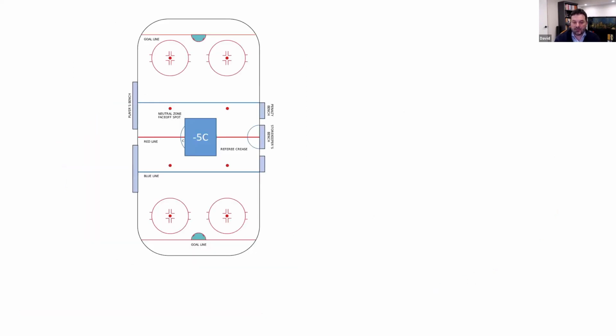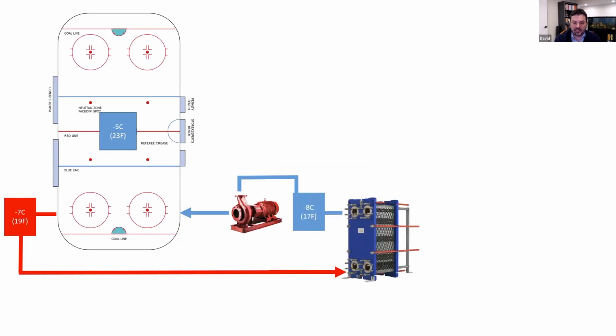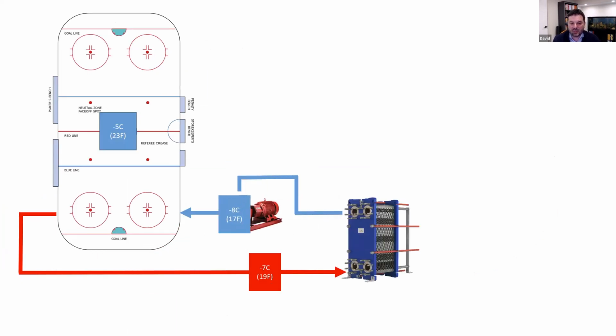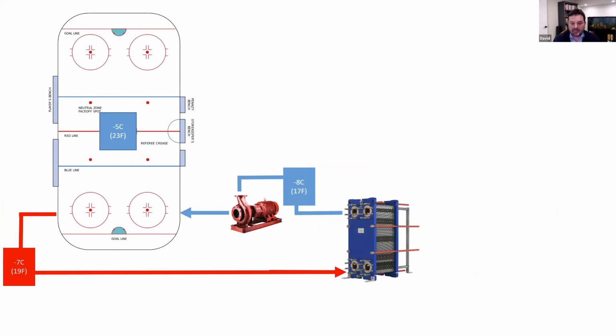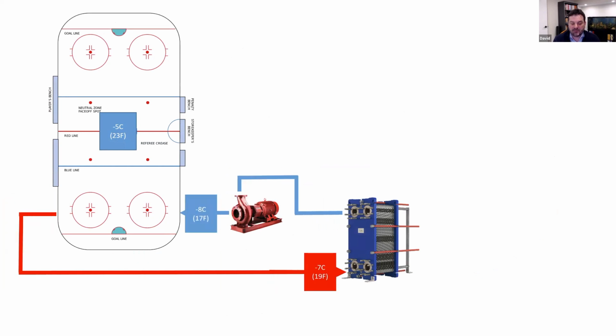If we take a look at refrigeration from a very simplistic view, there's a lot that goes into creating that perfect sheet of ice. A lot of ice makers will tell you that -5 Celsius is really the sweet spot from a refrigeration point of view. So to get that -5, we need to circulate a brine or glycol solution through the floor. As you can see, that red pump is pumping glycol out at -8 Celsius, or 17 degrees Fahrenheit.